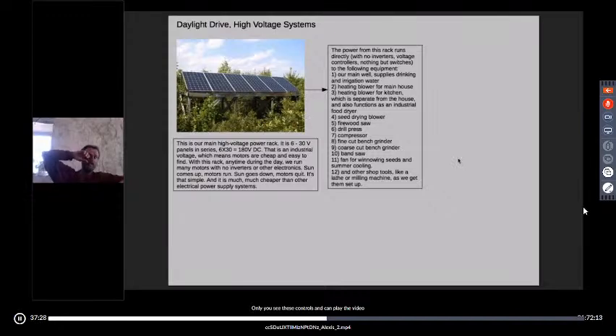Super simple, doesn't go wrong for the most part. I will warn you, what we've learned about DC electricity is that particularly as voltage drops in cloudy weather, that DC current beats up switches pretty bad. The current coming off this solar rack is about 8 amps, so you'd think a 10 amp switch would be fine. Well, that DC power will destroy 10 amp switches, and it will destroy 20 amp switches too. We're currently using 30 amp switches.